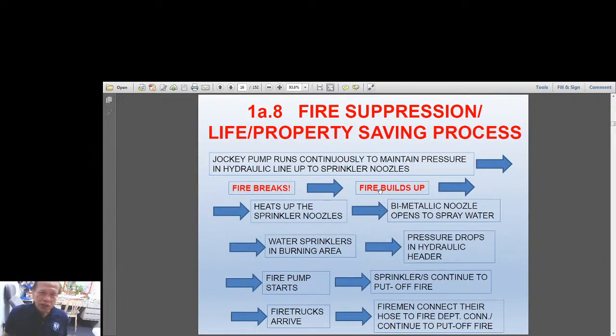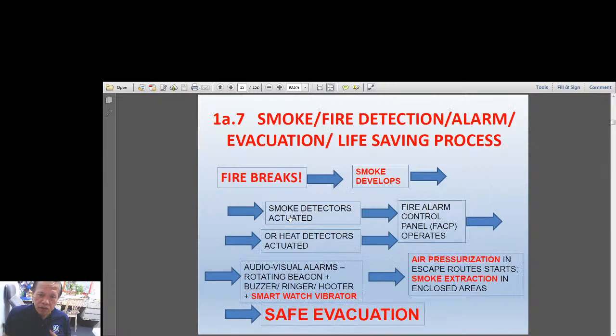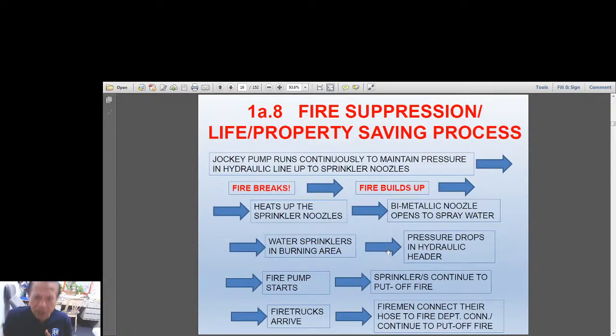Okay, so therefore the first slide is more of saving the people, the occupants of the building, while the second slide is more of saving the property, because the water in the sprinklers cannot save a person. If a person is still inside the building, chances are he will get suffocated, or he will be inhaling toxic gas like carbon monoxide and some others, and that will kill him. So therefore, it is the fire detection and alarm system that is life-saving.